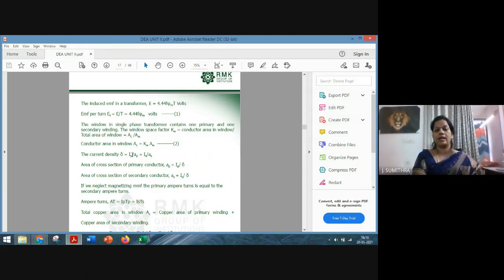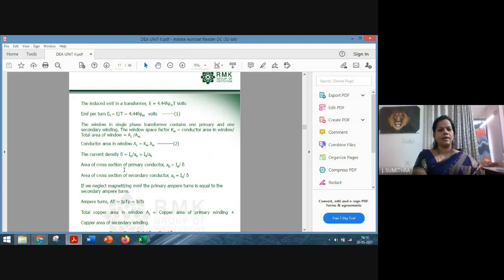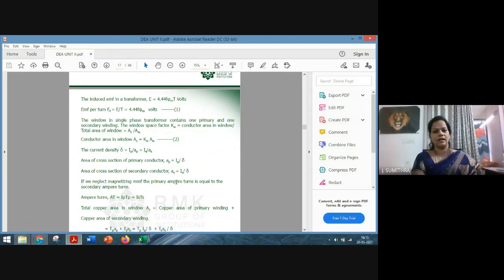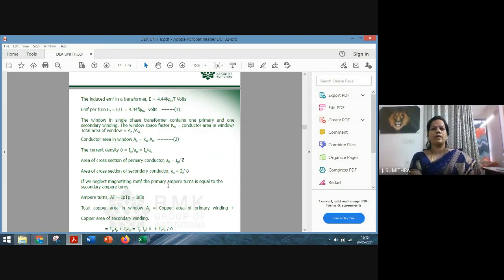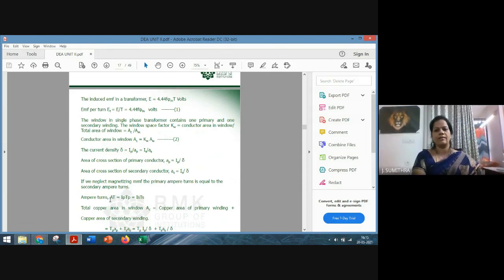The window in a single phase transformer contains only one primary and one secondary winding. We have a factor called the window space factor, which gives the ratio between the copper area and the window area, from which we get: copper area A_c = K_w × A_w. The current density δ is the ratio of current to the respective area of the conductor: A_p = I_p / δ for the primary, and A_s = I_s / δ for the secondary. Assuming the magnetizing MMF is negligible, the primary ampere-turns equals the secondary ampere-turns: I_p T_p = I_s T_s.